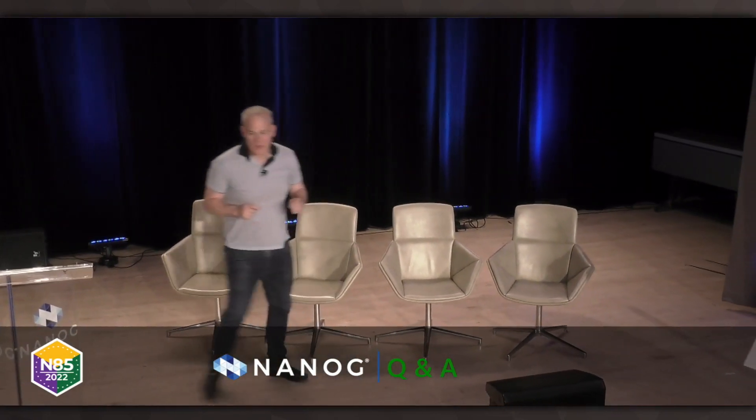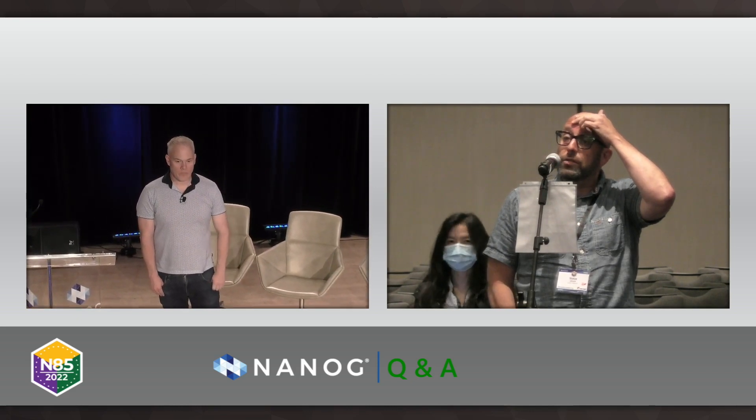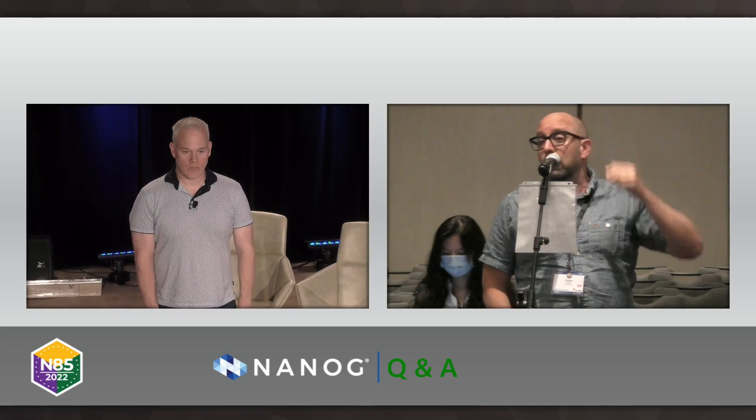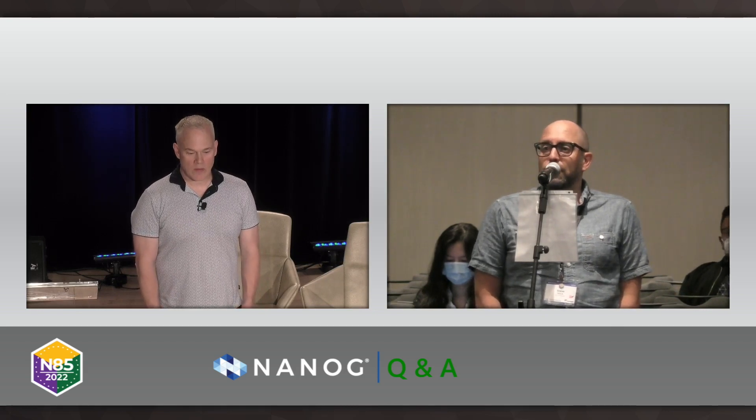Any questions for Lane? Steve Alwork, Arista Networks. Great presentation, Lane. I wonder if there's also a tangential conversation here around how willing folks are to embrace different physical form factors and hardware designs that might facilitate lower power consumption overall. A lot of times we have conversations with customers where they want to pack as much as possible into one RU, but if we made the box three RU it'd be a lot easier to cool. You're trading off one set of things for another, but you can spin fans slower and cool the box more efficiently. Speaking as a vendor, we're curious what trade-offs operators might be looking for in the future.